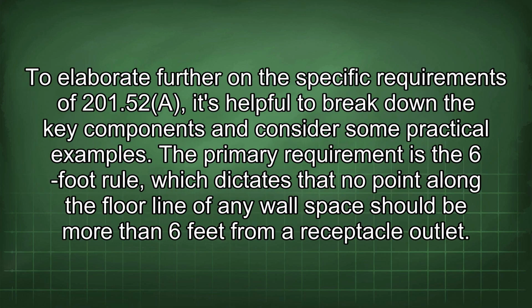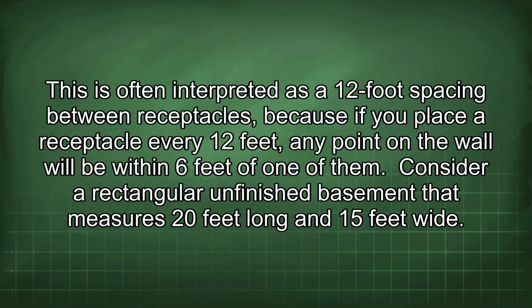To elaborate further on the specific requirements of 210.52(A), it's helpful to break down the key components and consider some practical examples. The primary requirement is the 6-foot rule, which dictates that no point along the floor line of any wall space should be more than 6 feet from a receptacle outlet. This is often interpreted as a 12-foot spacing between receptacles, because if you place a receptacle every 12 feet, any point in the wall will be within 6 feet of one of them.